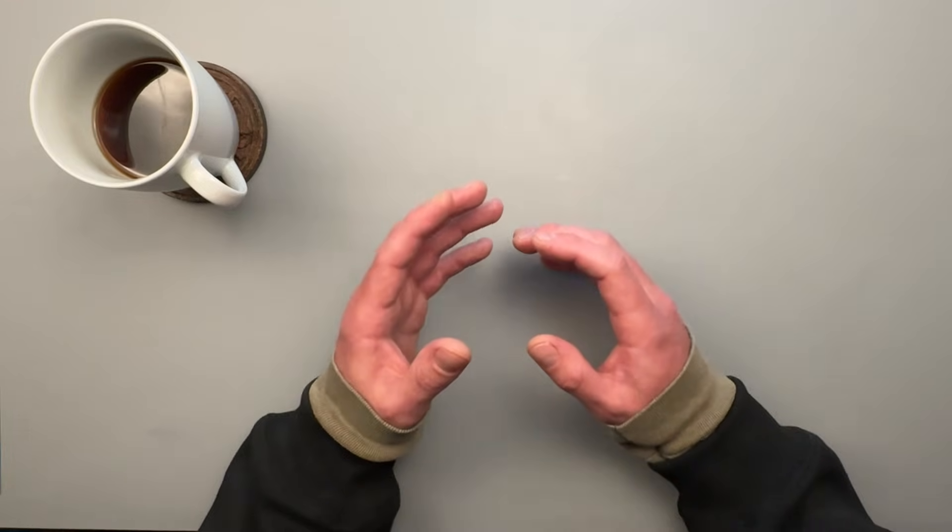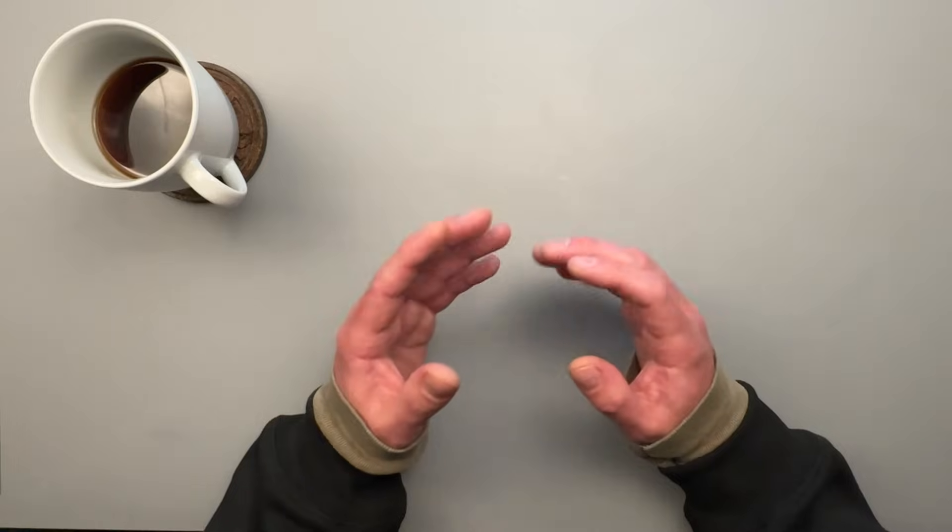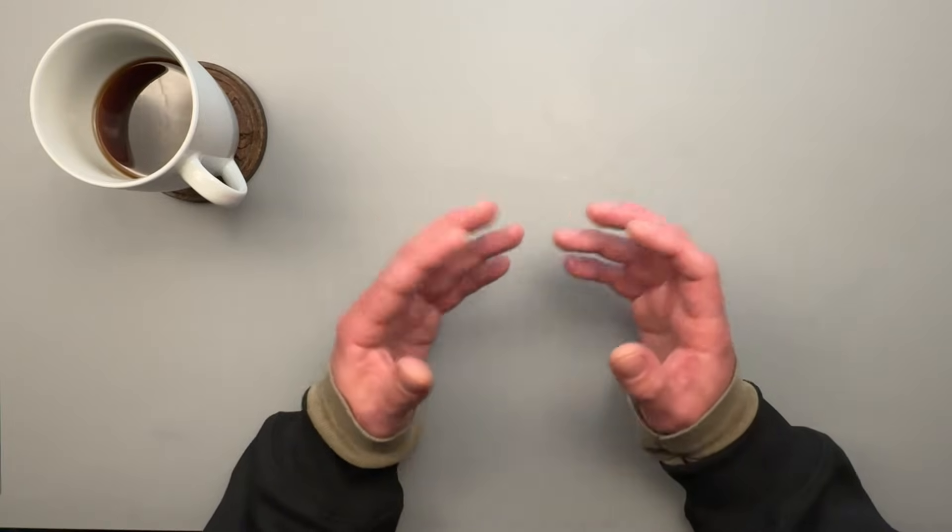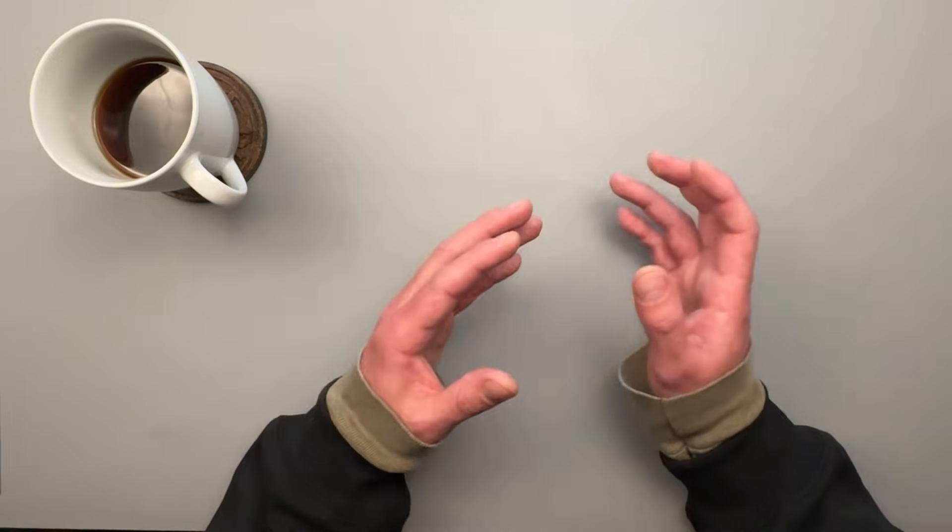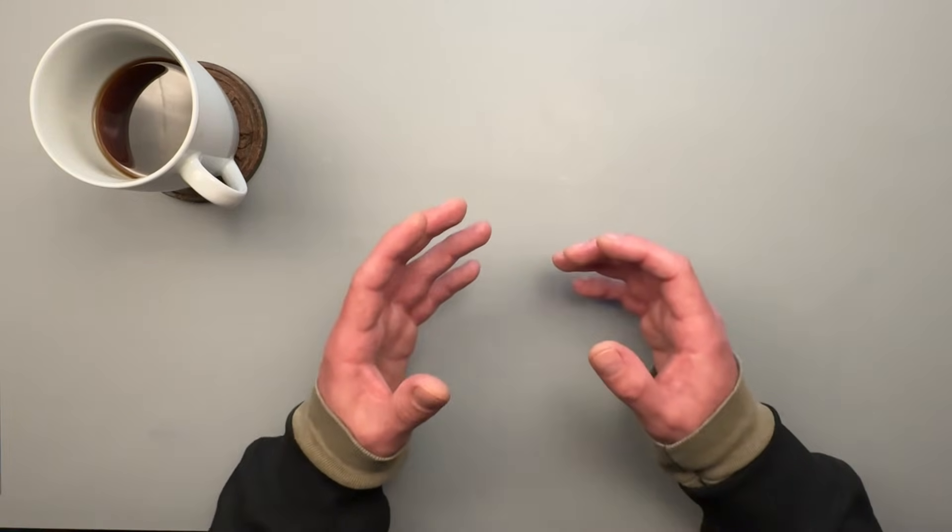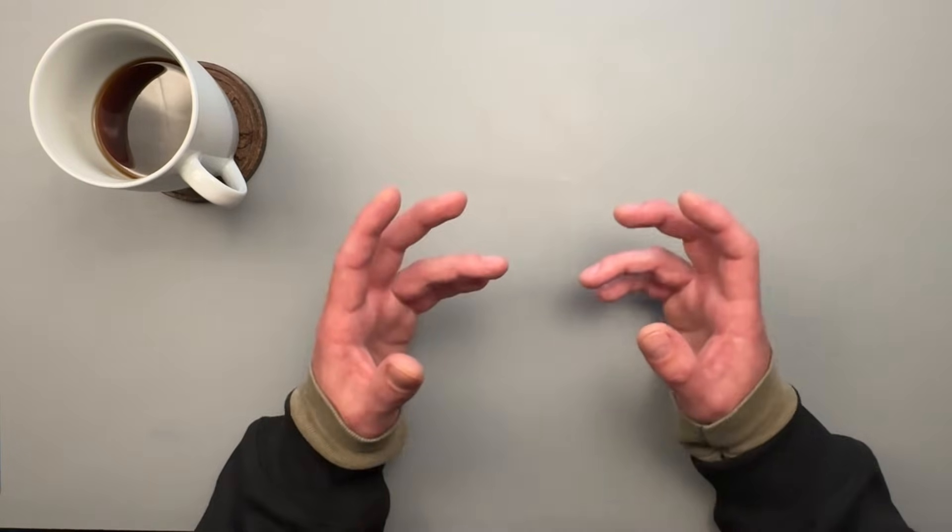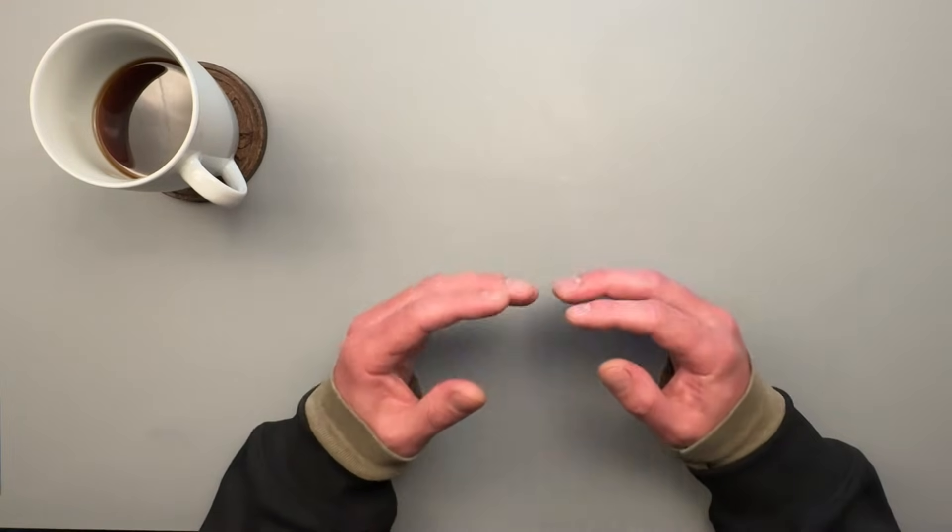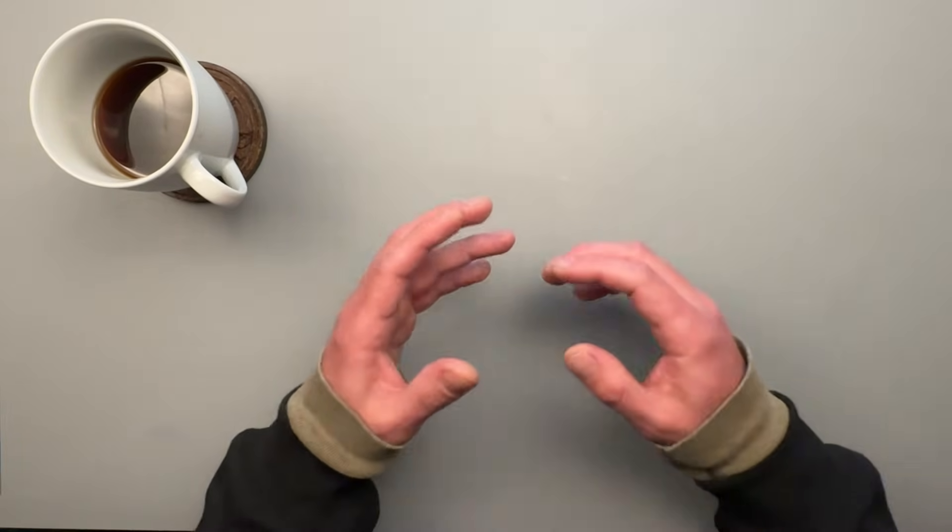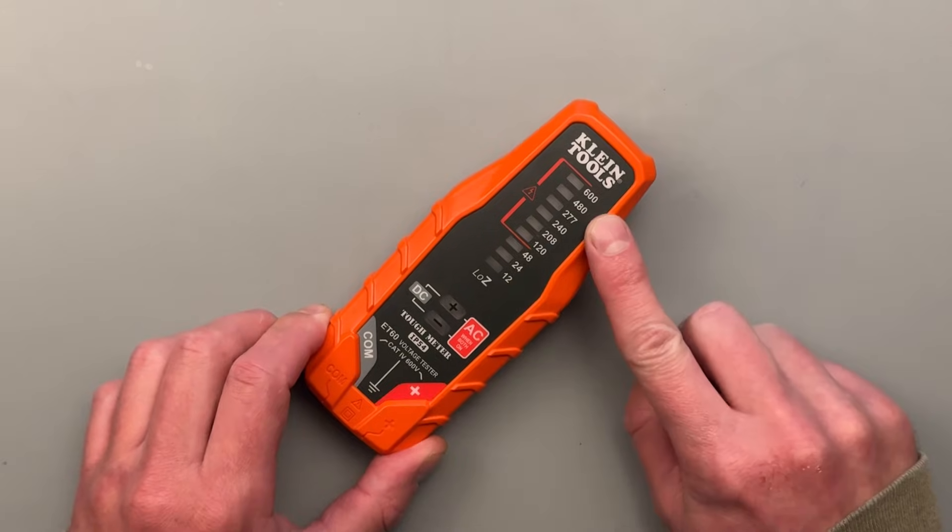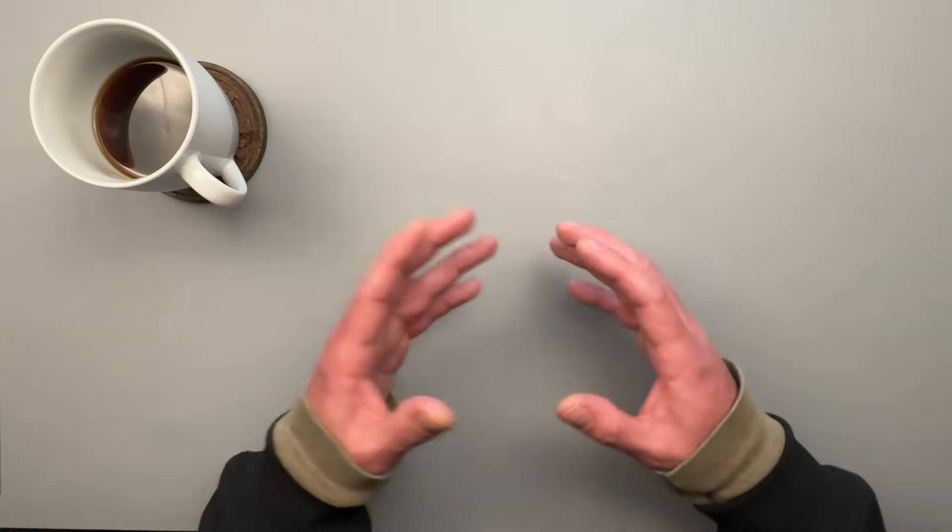Lastly, a lesser known meter is a solenoid voltmeter, aka a wiggy tester. If you're feeling a bit overwhelmed by the options and settings, that's completely understandable. A wiggy tester is extremely easy to use and doesn't even require batteries, making this the perfect tester to keep in the truck or RV for long-term storage. This device is meant for only checking if there is power being supplied to a component such as an outlet. They're able to reliably read between 12 to 600 volts AC and DC and is the perfect tool for a novice or beginner.